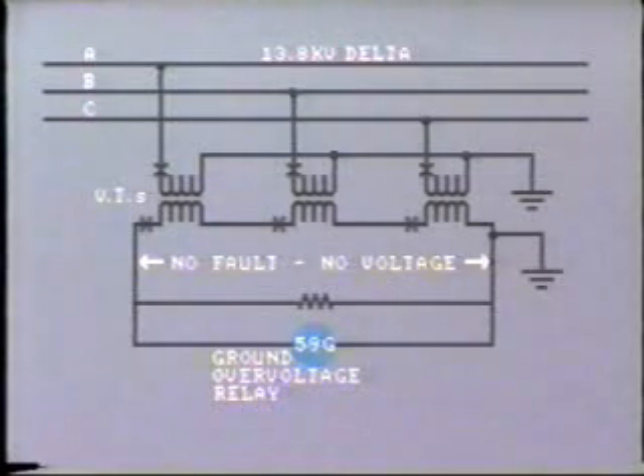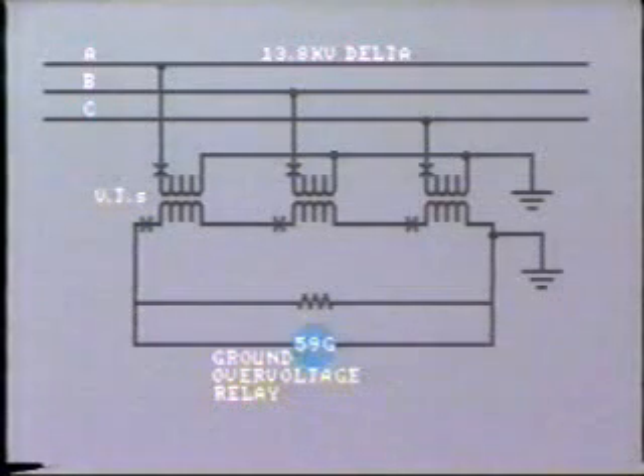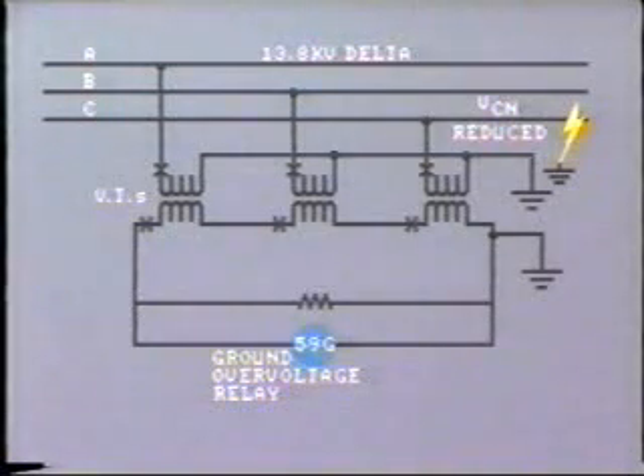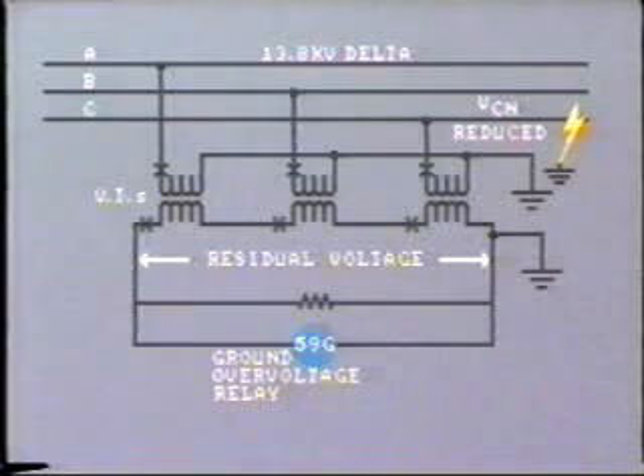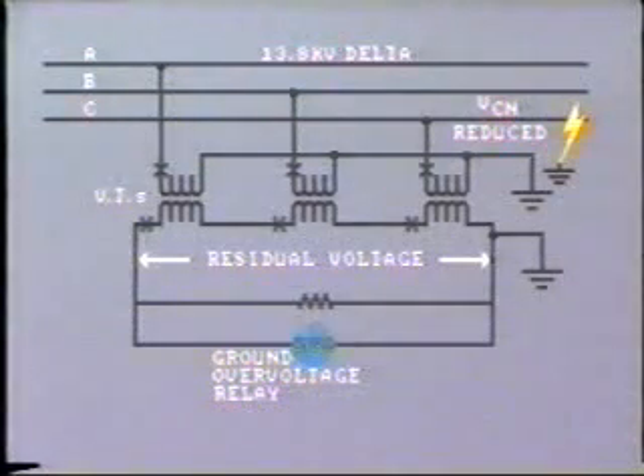If no fault exists, there is negligible voltage across the relay because the balanced voltages produced in the secondaries cancel each other out. Now, in the case of a ground fault on one of the lines, the voltage to ground on that phase is reduced. This reduces the voltage across the primary of that phase. This will cause a reduction of voltage in the associated secondary. Hence, a residual voltage will appear across the ground over voltage relay to cause operation.